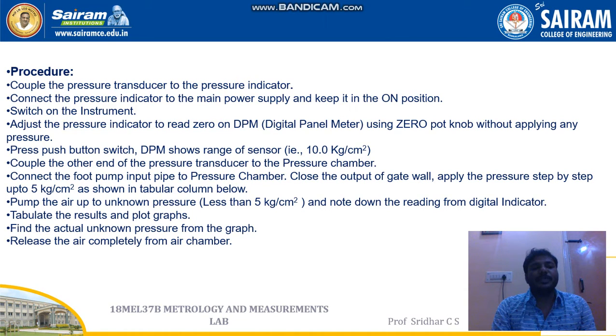The next step is to press the push button switch to show the range of the sensor, which is 10 kg per centimeter square. Then we couple the other end of the pressure transducer to the pressure chamber. Then we connect the foot pump inlet pipe to the pressure chamber. Once it is connected, close the output gate valve and apply the pressure step by step up to 5 kg per centimeter square, as shown in the tabular column below.